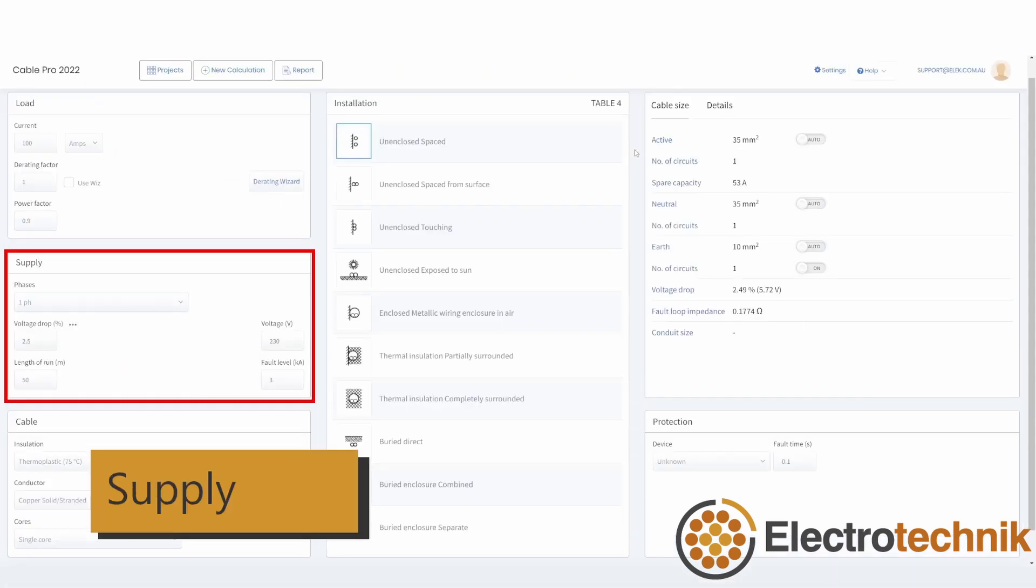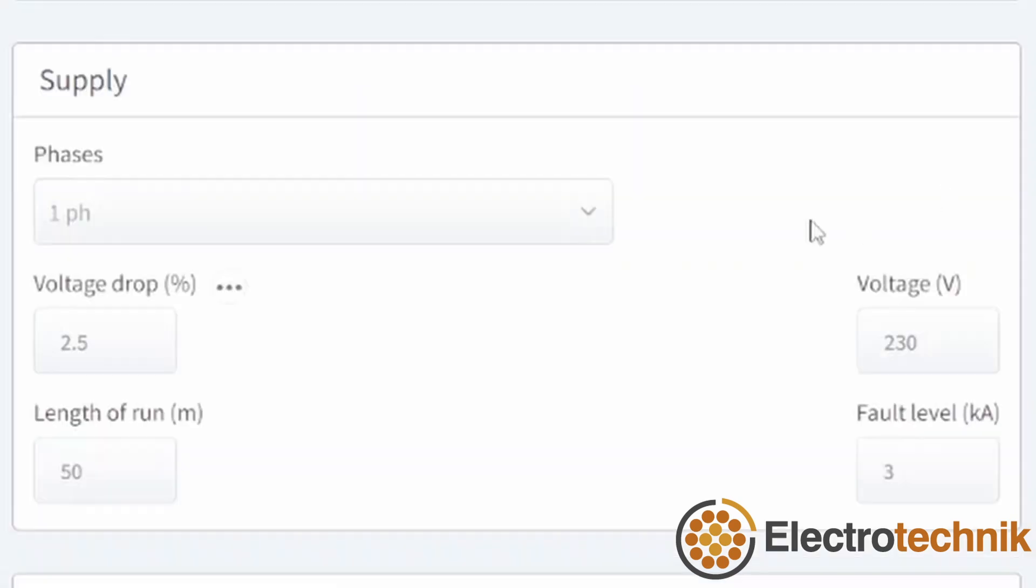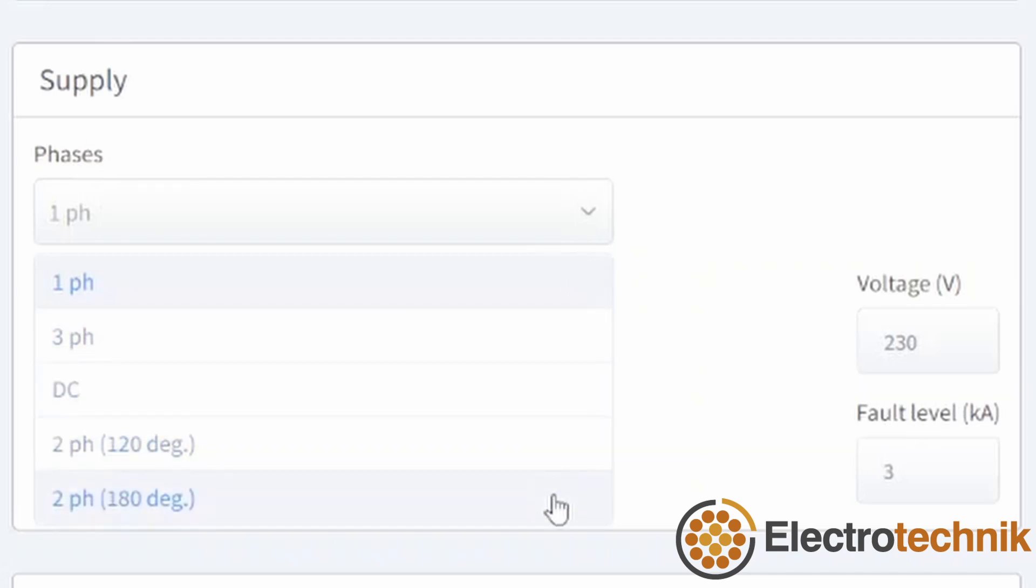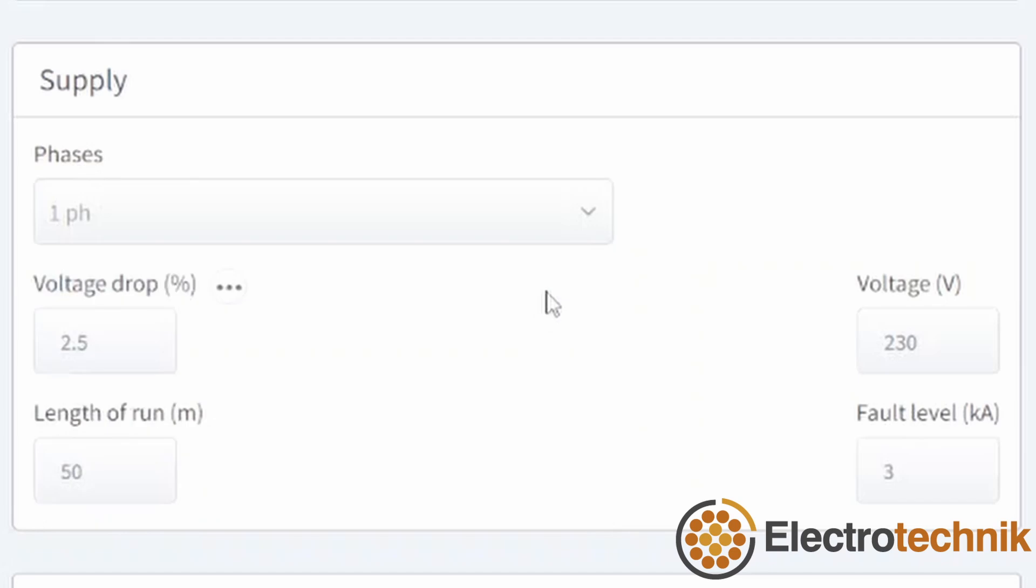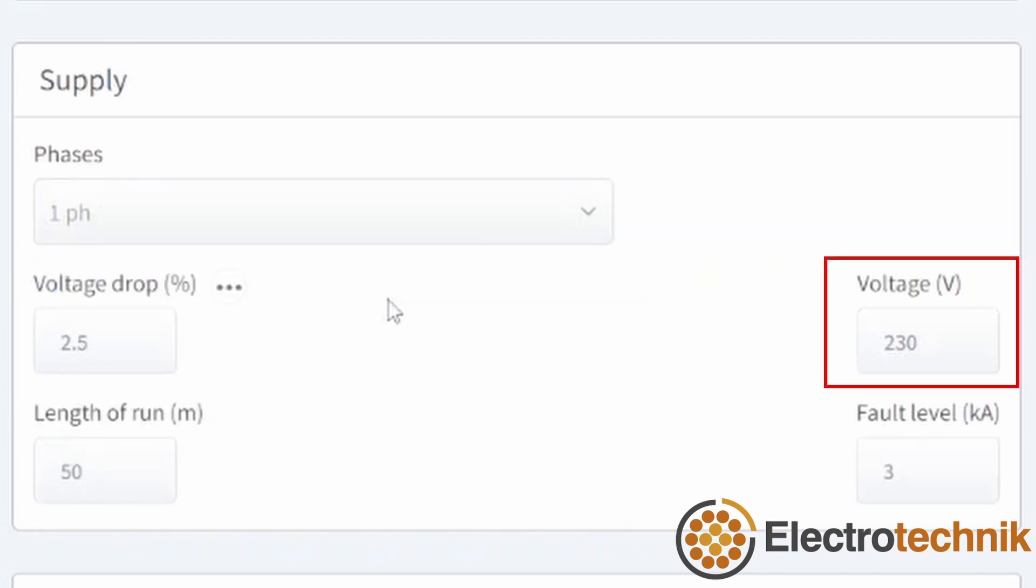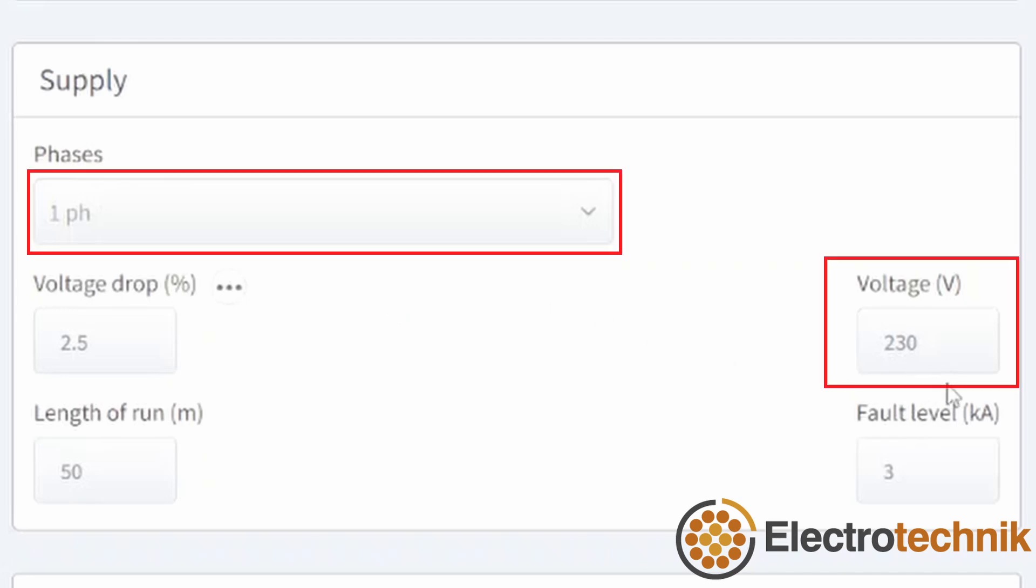Next up is the supply section. The phases can be selected as single phase, three phase, DC or two phase. This selection will affect cable size and voltage drop calculations. It will also change some of the options available in the other sections. Changing phases will update the voltage input. There are default voltages for each of the phase settings. For example, 230 volts for single phase.